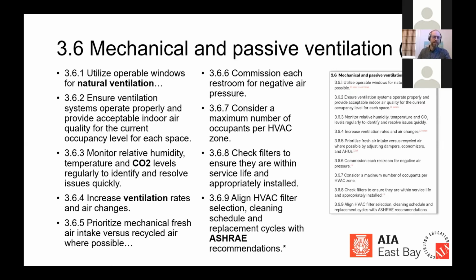The idea is that there is a background level of CO2 in the outside environment where we all live. And indoors, there's a higher level of CO2 because, when there are occupants in there, they're breathing. So the more CO2 there is, the more human breath may be comprising the air. One interesting thing to note with filters is that CO2 does not get filtered. When we talk later about MERV 13 and HEPA and everything, CO2 is a molecule that is still part of the air, even moving through those filters.